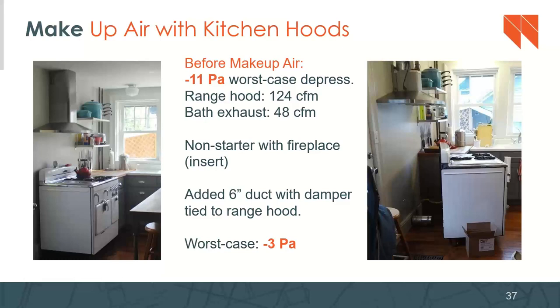So what was done: a 6-inch duct with a damper was added, and you can see it here underneath the stove. The stove actually rolls back and slides on top of this duct. It has the damper, it's wired to the range hood, so when the range hood comes on, the damper opens. The worst case depressurization, with the range hood on, the bath exhaust on, and the dryer on, was reduced to just 3 Pascals of pressure from inside to outside.